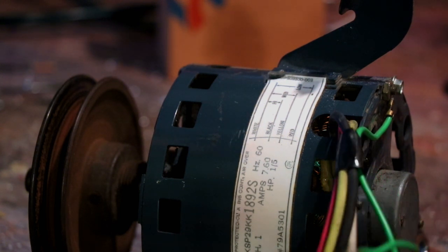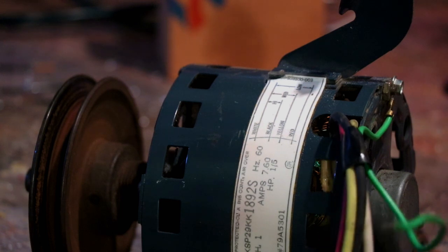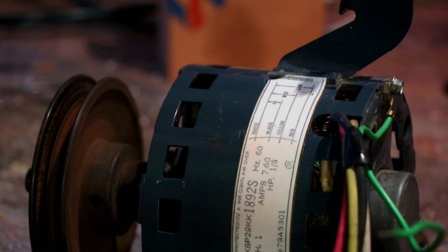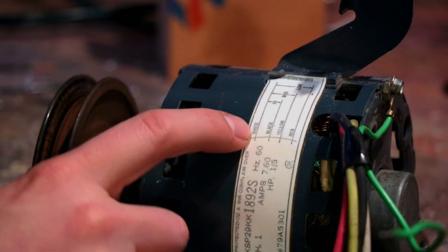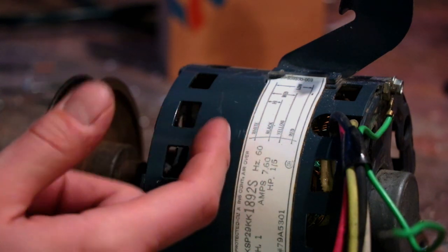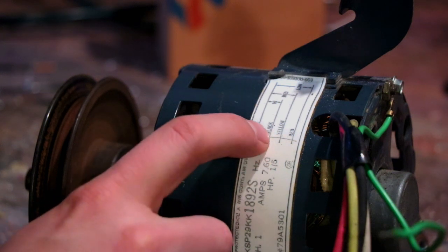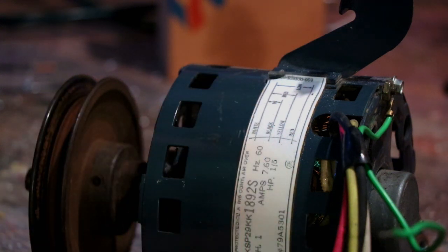So to wire this thing up, I could actually just wire one speed at a time. To do that you would just wire, say you want to only run high speed, you would wire your white to white neutral from the line and then you would wire your hot wire from the line to black and you'd have high speed only and you'd just cap your other two wires.